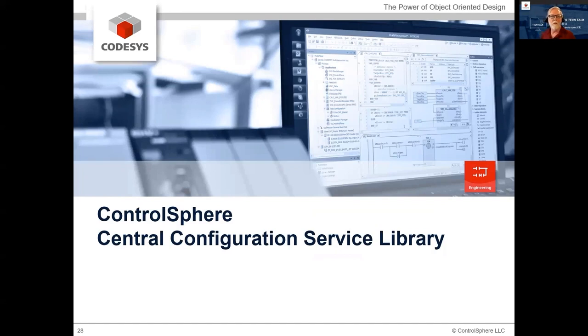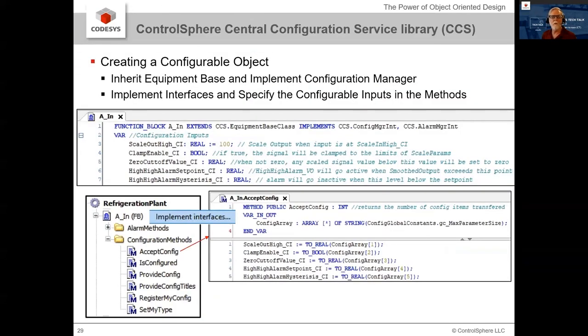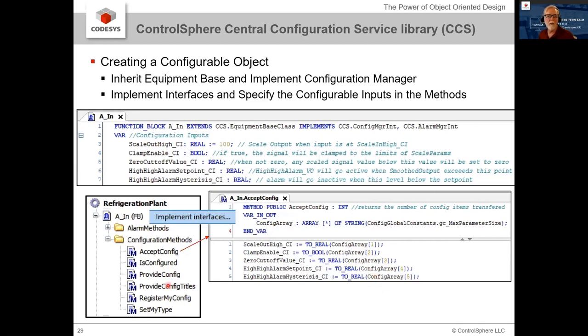Let's talk about the configuration central service library. To become a configurable object, the function block needs to extend the equipment base class and implement the config manager interface. CODESYS provides a great feature: you right-click on the function block, say 'implement interfaces,' and it puts them all in there for you. Then you just write the code that takes the array of strings and puts the variables where they need to go, and do the same on the provide config side in reverse. The titles method tells the system what to fill in at those column headers. This could be greatly simplified with some platform automation.